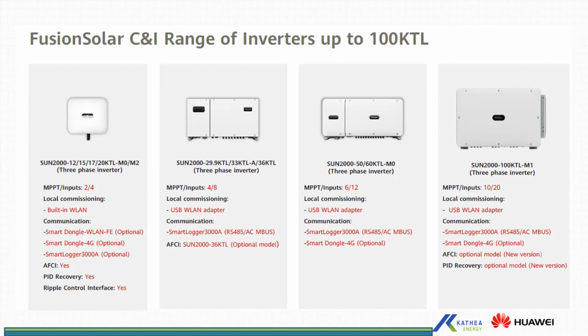So if you have a 100 KTL inverter, it can produce up to 110 kilowatt, and a 20 up to 22, and so on. For the 12 to 20 range, our inverters have 2 built-in MPPTs with two strings per MPPT. It means you can wire 4 strings on these inverters. The good part about the 12 to 20 KTL range is they also support optimizers. We'll also touch on that later on. You can actually have long strings on the system by utilizing optimizer technology. And then the next range, which is the 29 to 40, has 4 MPPTs. That is four strings. And then the 50-60 has 6 MPPTs with 12 strings. And then the 100 has 10 MPPTs, and you can wire up to 20 strings on it.